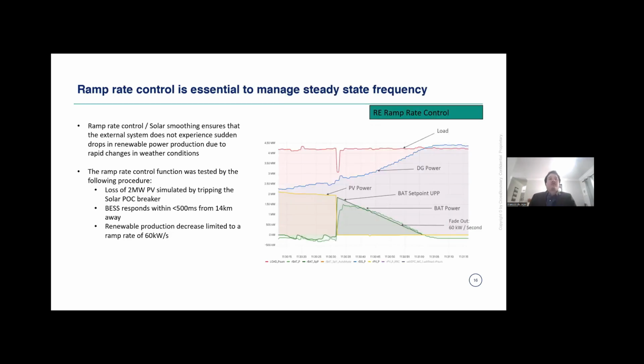So diving specifically into the ramp rate control and some data that we collected during the commissioning exercises, it's essential that we apply this ramp rate control application within microgrids and weak grids in general, looking at the intermittency of solar. If we all of a sudden have a cloud cover going over our plant and we lose the bulk of our solar PV, we could sit with decaying frequency or rate of change of frequency that falls beyond what the grid can handle, and we can very quickly see a grid collapse if our solar penetration was reaching levels above what our genset step change can handle.